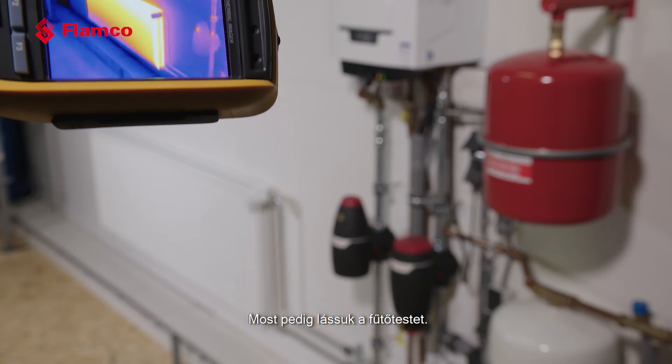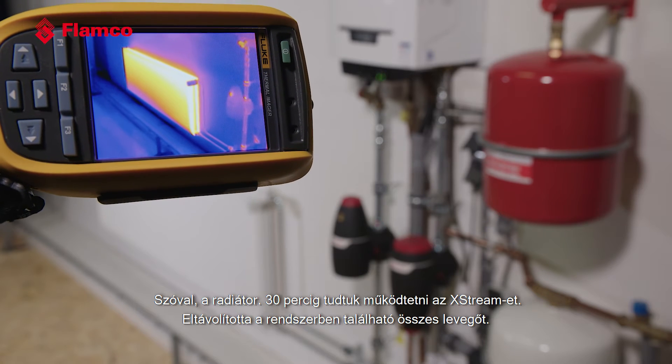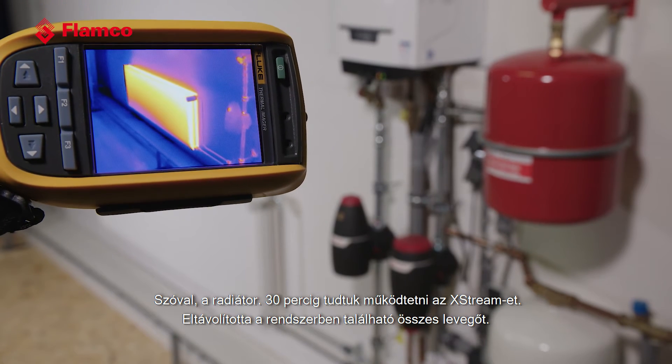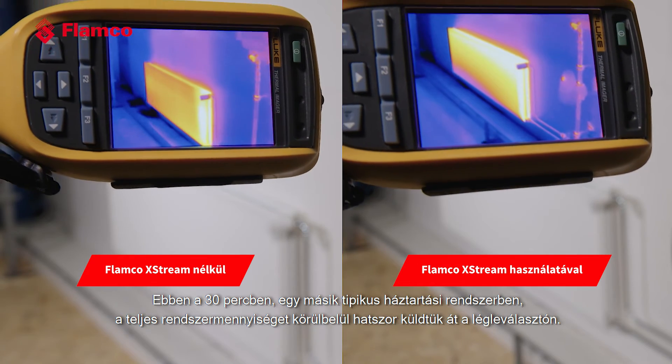Let's have a look at the radiator. So the radiator now — we've been able to run the XStream for 30 minutes and it has removed all of the air that was in the system. In that 30 minutes on a typical domestic system we've run about six times the total system volume through the vent.